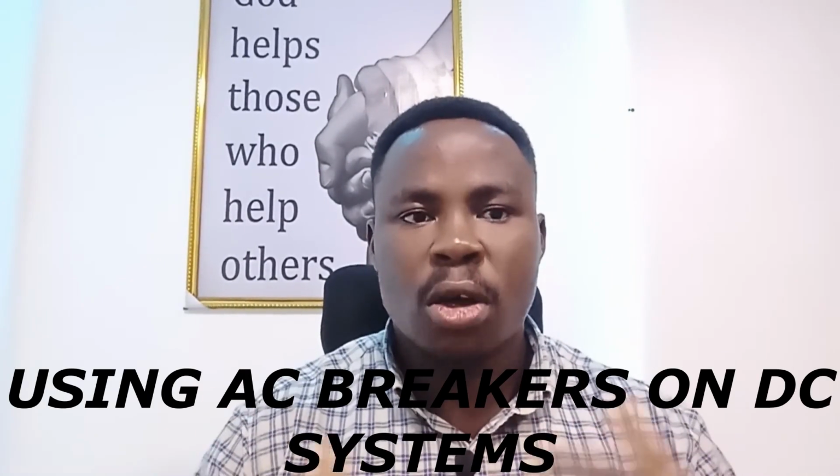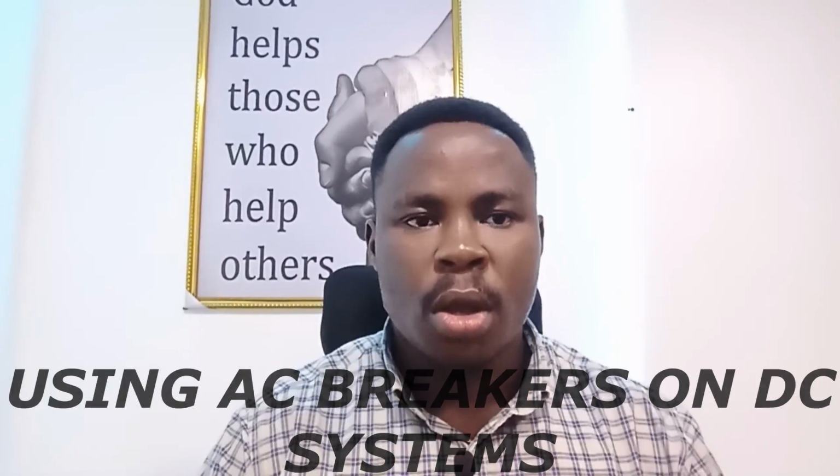Number four mistake is using AC breakers on DC systems. This is more dangerous than most people think. AC breakers can't handle DC current. In AC systems, current naturally drops to zero many times in a second, while in DC systems, current flows continuously, which means that when DC arcing starts, it's much harder to stop.